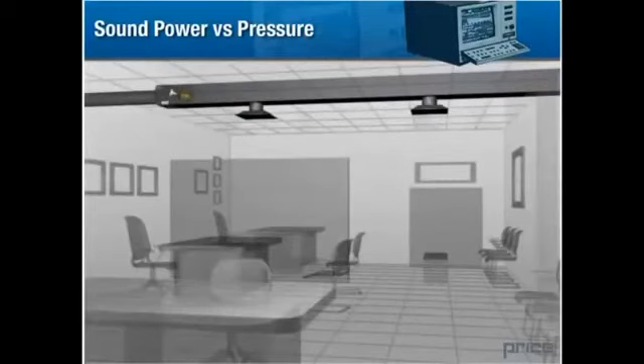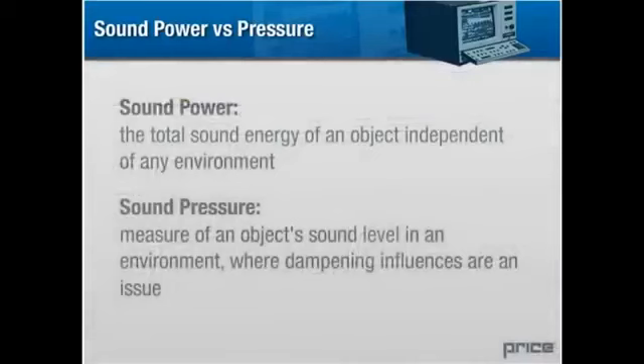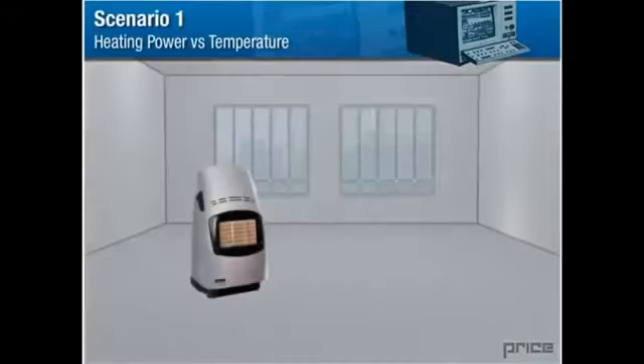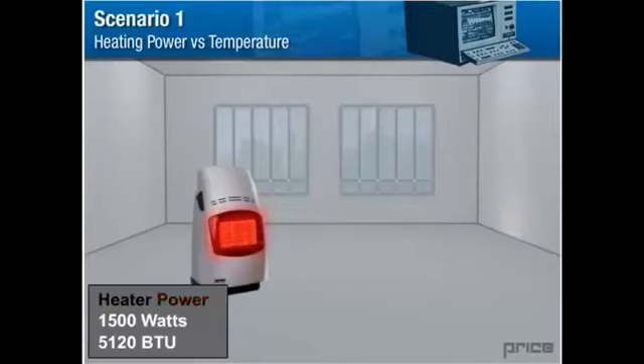Although catalog data provides a basis for product comparisons, the environment into which an HVAC system is installed can greatly affect noise levels perceived by its inhabitants. In order to understand the difference between sound power and sound pressure, let's take a look at three similar scenarios. Consider the analogy of a heater's warming effect on a room. The heater's heat output or power is rated in either watts or BTUs. This power output will remain constant.